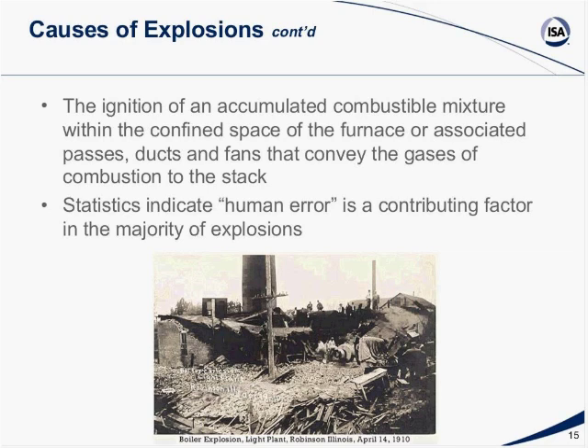This is going to be a few slides showing explosions and some of the conditions of these explosions. An explosion is the ignition of a combustion mixture within the confined space of the furnace or associated passes, ducts, and fans that convey the gas of combustion to the stack. Statistics indicate, as I just pointed out, human error is a contributing factor in the majority of explosions. This picture right here was in 1910. I was at the company that owned this boiler, and they weren't sure what happened, but they were pretty sure it was a gas explosion. Gas explosions tend to do a lot more damage than other types, such as coal dust. Gas explosions do a great deal of damage, and many people are killed as a result.